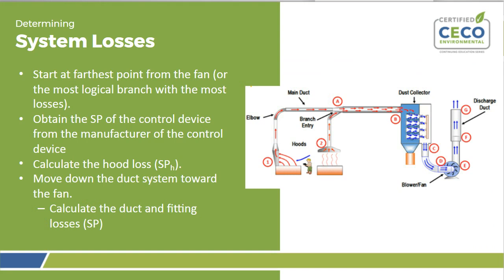Determining loss, you want to usually start from your furthest point. You're hoping that's your governing leg. I like to check all of them near the end of the line. In this case, we're going from point 1 at the hood up to point A. We get a static pressure. Then we calculate the loss from point 2 to A, and you pick whichever is higher. That's your governing static pressure. Then you add from point A to B. You add for the dust collector, which in this case is a cartridge style filter, and typically that's in the 5-inch range.